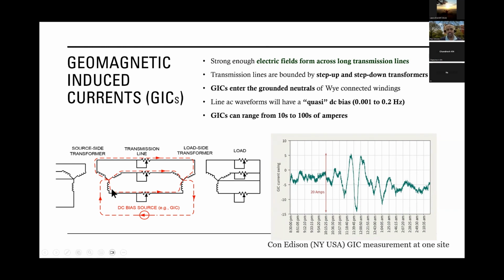Now what you have is a DC current superimposed on an AC waveform. The power system, the transformer, was not designed to operate in that manner, it was designed to operate on alternating current without a DC component in it. This DC current, as I mentioned, is very low frequency, and the GIC that can flow can range from tens to hundreds of amps along power lines. The power line itself is carrying the normal load current for the load it's serving. Now it's also called to carry the load current plus the GIC, and that can cause very detrimental effects, which I'll go into.